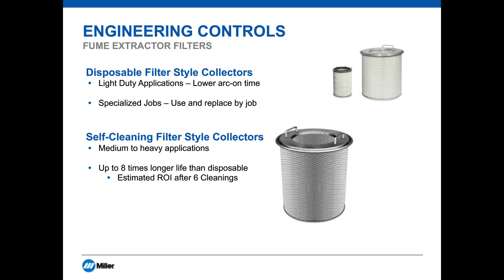Some other items that may affect the filter are quantity of fume, type of fume, cleanliness of part, hours of operation, and cleaning cycles. What I mean by this is that TIG is different than MIG welding versus stick welding. There is more fume generated during stick welding, more particulate than there would be during TIG. It also depends on whether you're welding mild steel or stainless. All items come into play when you're looking at filter types and quantity of filters.